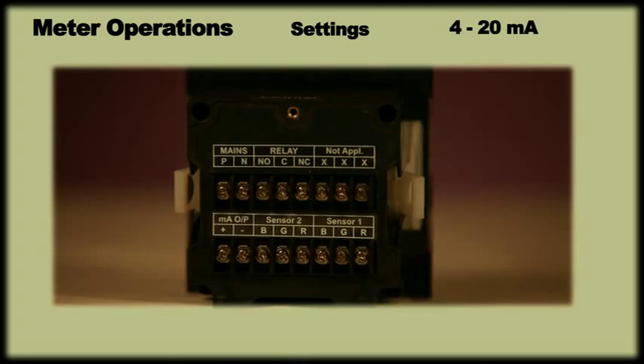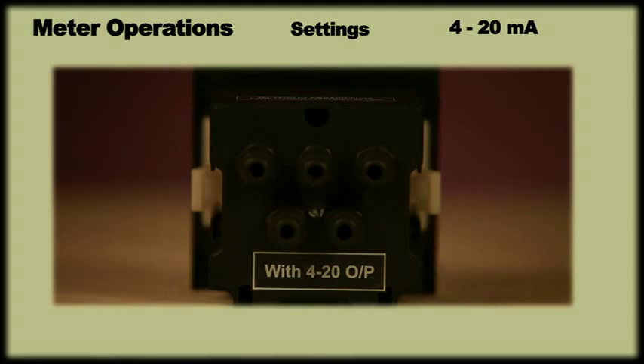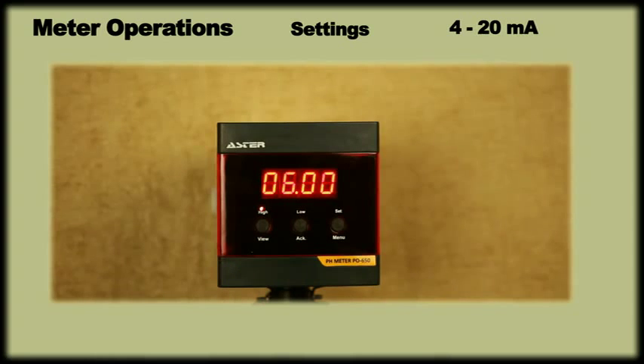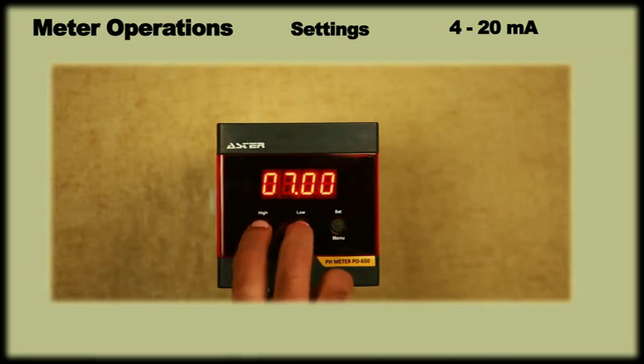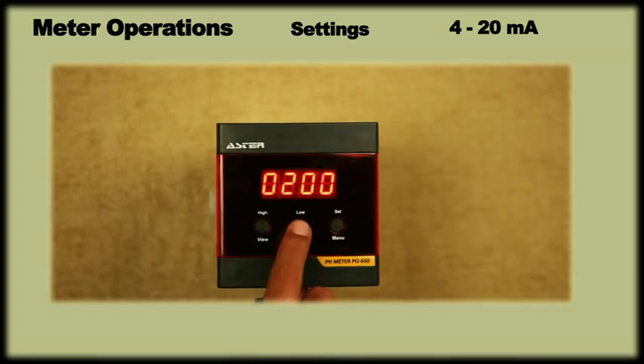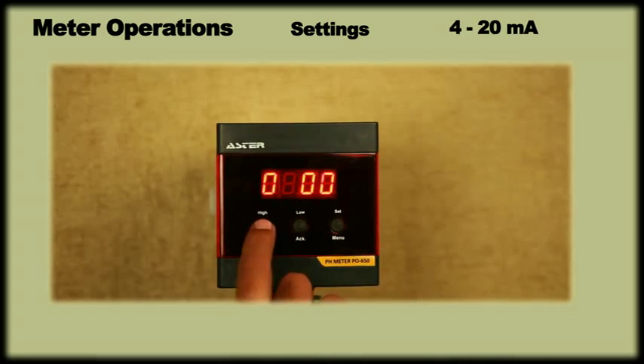In case your meter has 4 to 20 mA output, the default 0 and span setting can be viewed by pressing View key and output current of the moment can be seen by pressing ACK key. In case the factory setting of 0 and span needs to be changed based on the process requirement, press View and ACK key simultaneously and enter password 0678.